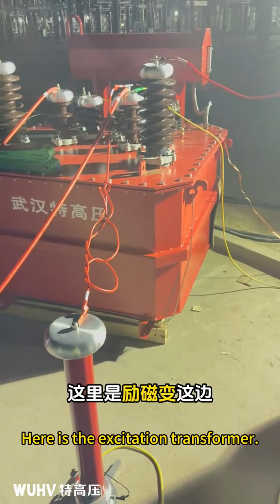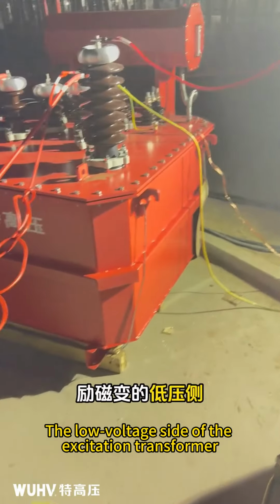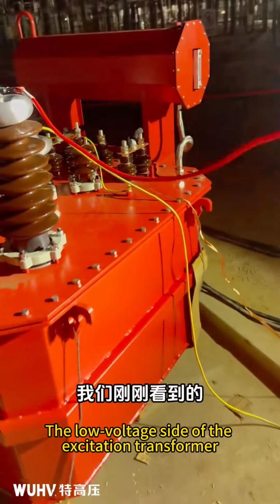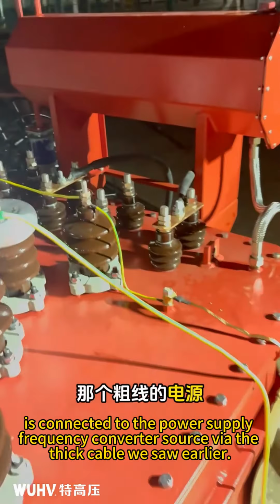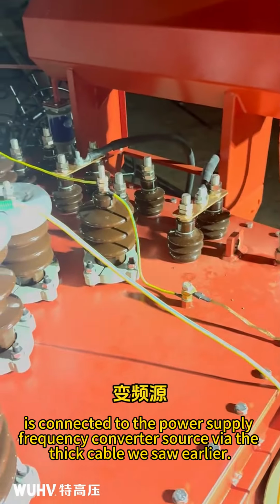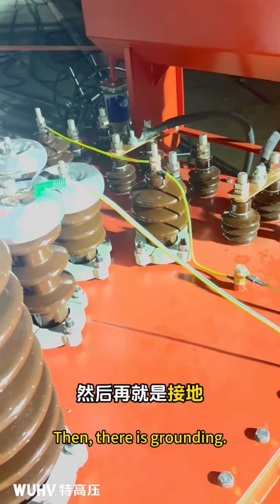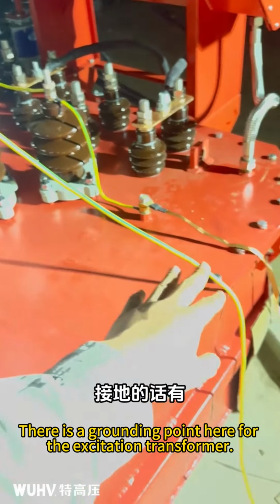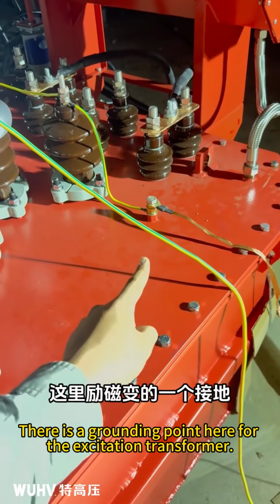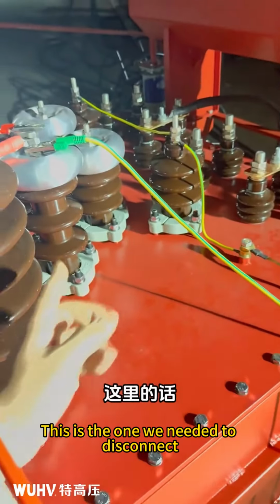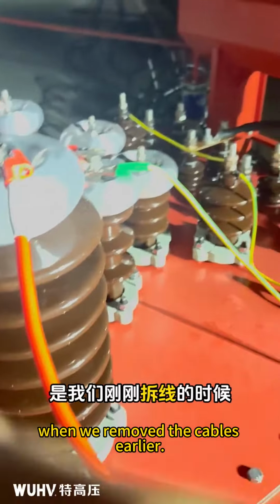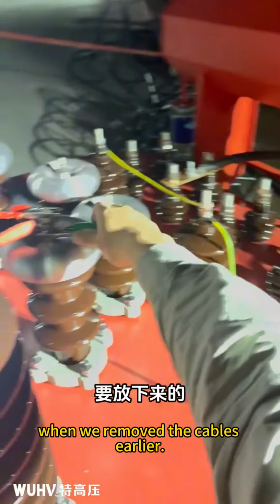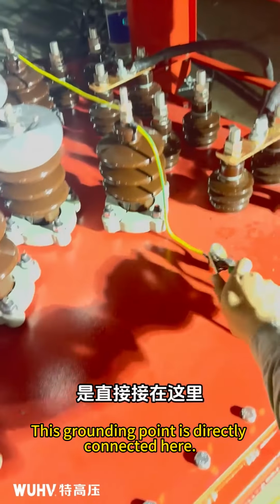Here is the excitation transformer. The low voltage side of the excitation transformer is connected to the power supply frequency converter source via the thick cable we saw earlier. Then, there is grounding. There is a grounding point here for the excitation transformer. This is the one we needed to disconnect when we removed the cables earlier. This grounding point is directly connected here.